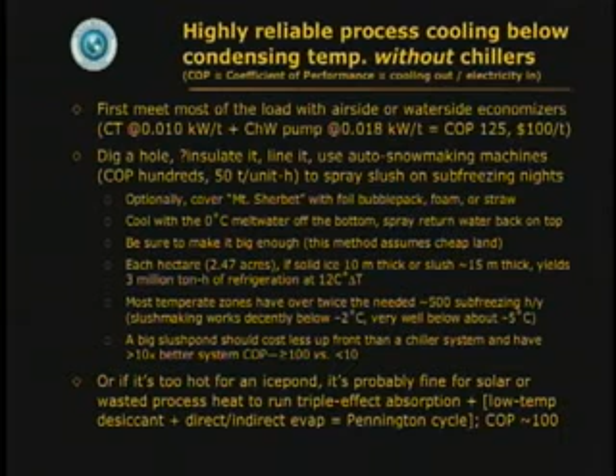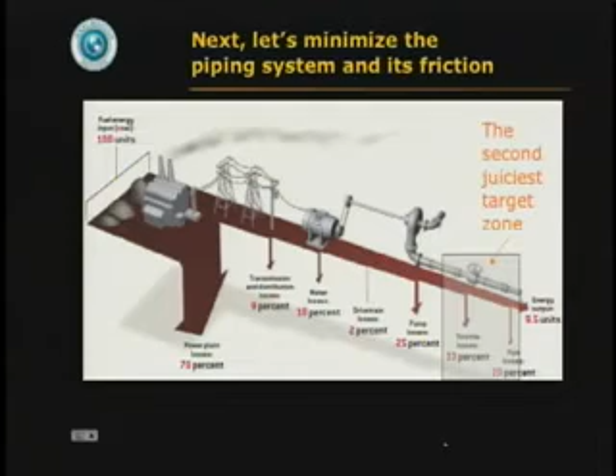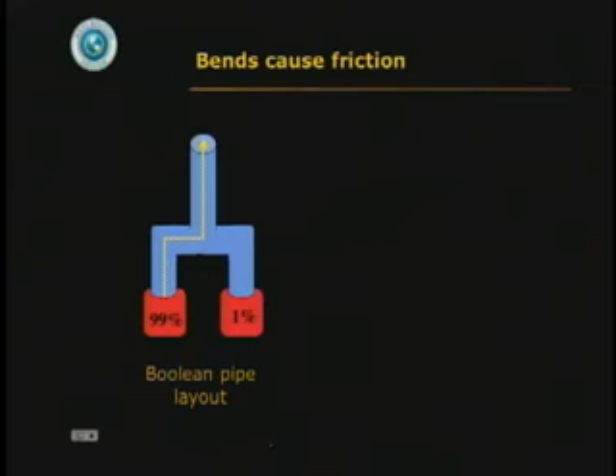Now let's go back upstream from reducing flow and friction, or reducing flow rather, to the next step, which is reducing friction in the pipes and valves. A good way to cause friction is to have bends. How often do we see a big pump that's supposed to send something up a pipe, but because it needs a partner or it's a very important pump that needs an in-place spare next to it, they draw something like this and then build it like this. So all the time the flow has to go through 2 right-angle bends and usually 2 valves. How about doing it this way with no bends and no valves or 1 valve?